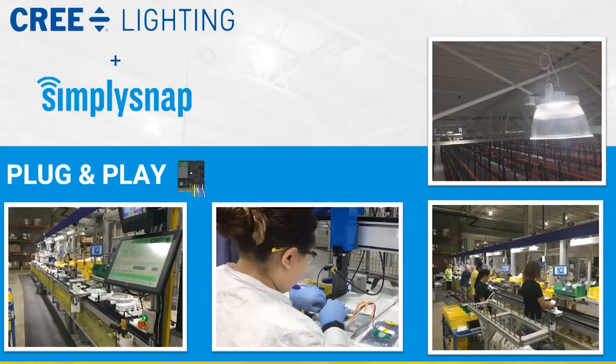Yeah, and one of the things I would really emphasize is the end-of-the-line testing that we do when we're adding the SimplySNAP system. We're already doing a lot of end-of-line testing for the standalone fixture, making sure this fixture is delivering the correct lumens that's being ordered, as well as the correct wattage, the correct CCT as well as CRI, and that everything the customer expects to get is coming off the line and that it works before it is ever put into a package and leaves the factory.